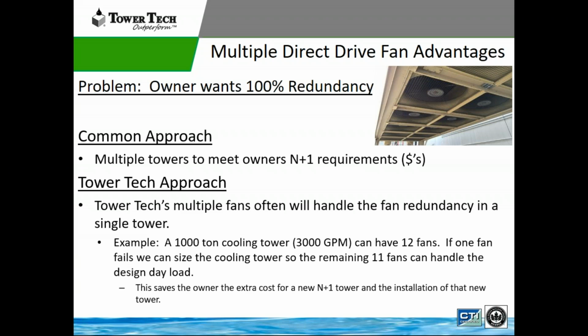The TowerTech approach is we're going to use the multiple fans to our advantage in the system. So let's look at an example where we have a 1,000-ton cooling tower, 3,000 GPM. We're going to put 12 fans in that. Now, that's the largest fan system we offer on the cooling tower system. So if one fan fails in the system, we're able to operate at 100% capacity with 11 fans in the system. Okay, so this will allow the end user to save in footprint, install cost, controls, everything on a system by going to this. Once we hit that point, this system is obviously paid back versus a traditional system.